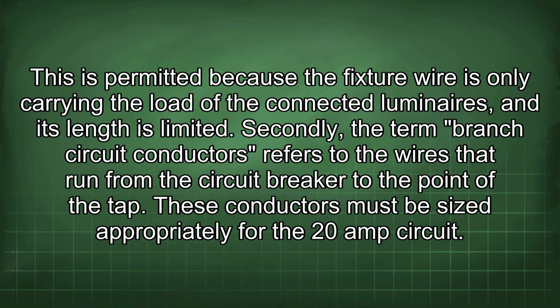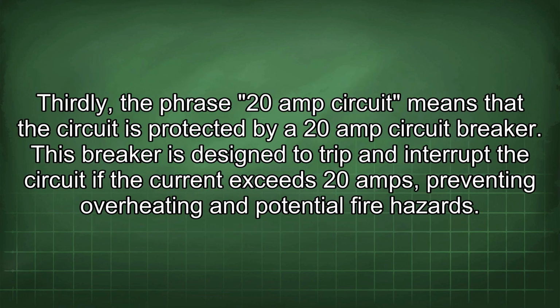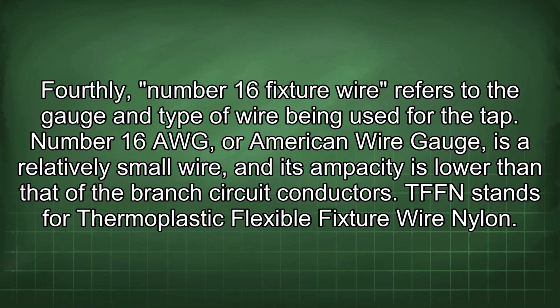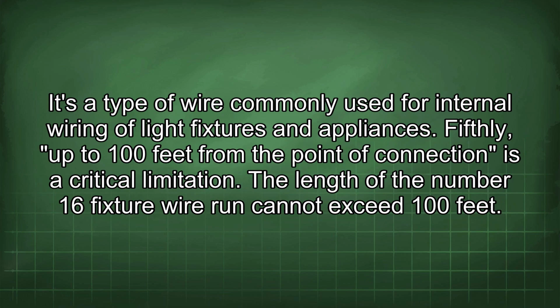These conductors must be sized appropriately for the 20-amp circuit. Thirdly, the phrase 20-amp circuit means that the circuit is protected by a 20-amp circuit breaker. This breaker is designed to trip and interrupt the circuit if the current exceeds 20 amps, preventing overheating and potential fire hazards. Fourthly, number 16 fixture wire refers to the gauge and type of wire being used for the tap. Number 16 AWG, or American Wire Gauge, is a relatively small wire, and its ampacity is lower than that of the branch circuit conductors. TFFN stands for thermoplastic flexible fixture wire nylon. It's a type of wire commonly used for internal wiring of light fixtures and appliances.